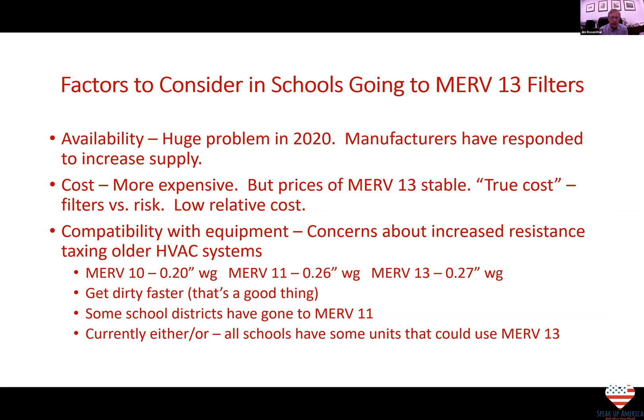Availability has been a challenge. MERV 13 was only 5% of the market, but in 2020 demand went to 40% of the market, and you couldn't get MERV 13 filters. A major manufacturer has since upped their capacity, so that should not be as much of a problem this year — that's not an excuse school districts and universities can use. On cost, it's definitely more expensive, but MERV 13 prices are stable. You have to consider the true cost: the cost of the filters versus the risk involved — it's a very low relative cost. Regarding compatibility, the concern is that increased resistance of MERV 13 filters will tax older HVAC systems.